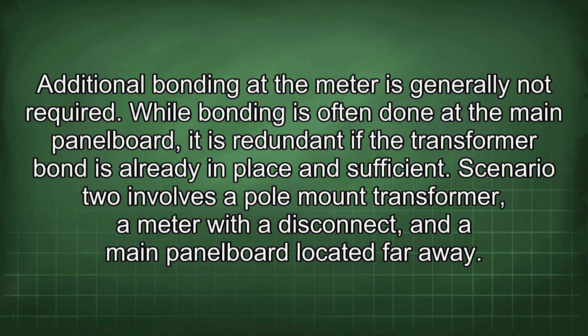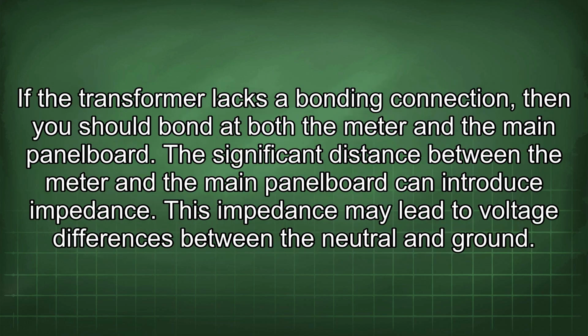place and sufficient. Scenario 2 involves a pole mount transformer, a meter with a disconnect, and a main panel board located far away. If the transformer lacks a bonding connection, then you should bond at both the meter and the main panel board. The significant distance between the meter and the main panel board can introduce impedance. This impedance may lead to voltage differences between the neutral and ground.